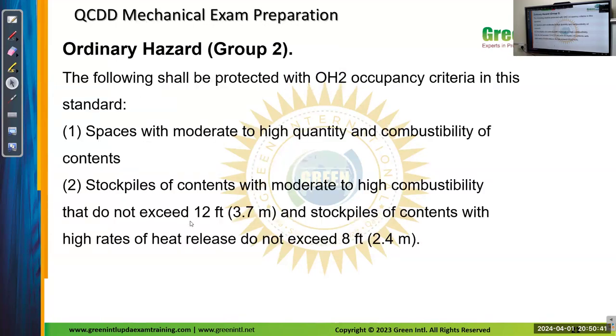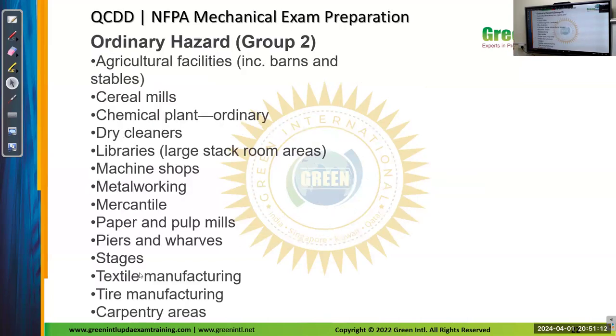So in ordinary hazard group 2, spaces have moderate to high quantity, and the combustibility of contents is greater. Stockpiles do not exceed 3.7 meters for contents with moderate rates of heat release, and do not exceed 2.4 meters for contents with high rates of heat release. These are the criteria to identify an area as ordinary hazard group 2. These are the areas under ordinary hazard group 2: agricultural facilities, cereal mills, chemical plants, dry cleaners, libraries, machine shops, metalworking, mercantile.